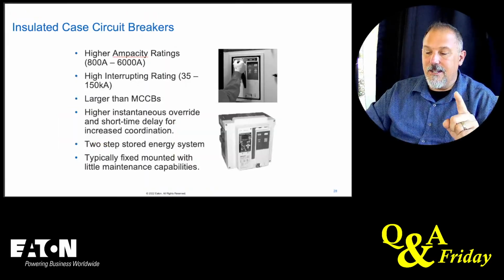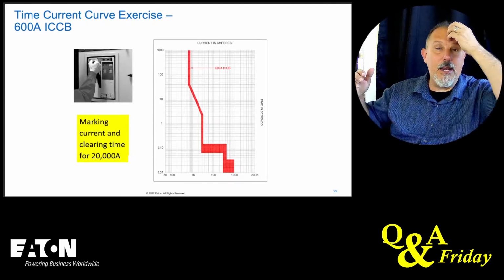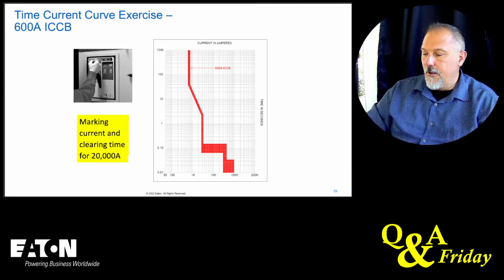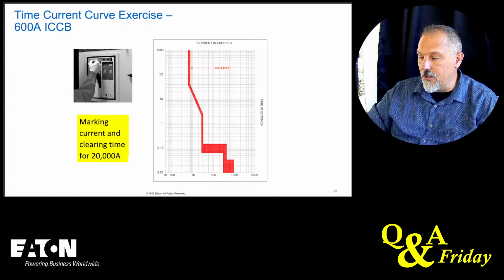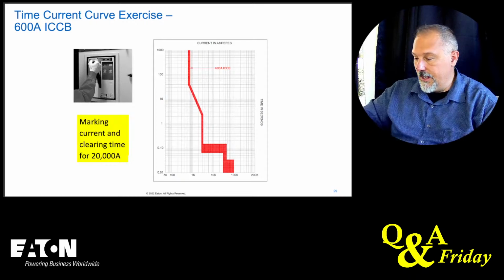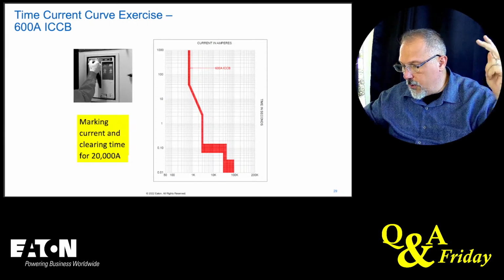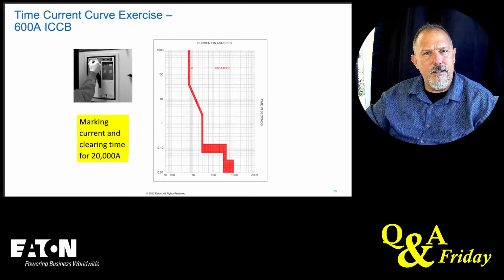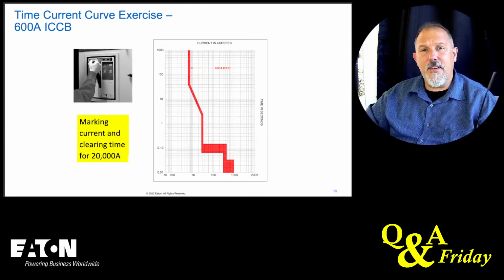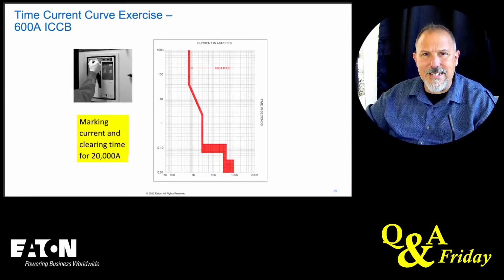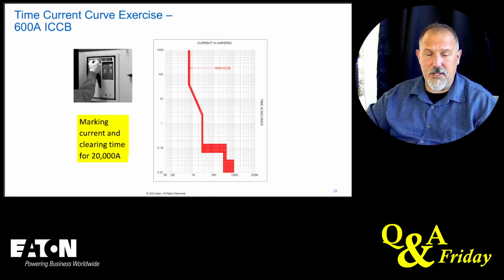Now, an insulated case circuit breaker, 600 amps. So this would be like an 800 amp frame adjusted down to 600. There's your point. That's actually 0.1. There's 0.2. So you're actually around 0.16 seconds. Definitely not current limiting here, but look at the instantaneous region. Your instantaneous region is 0.01, 0.02, 0.03 seconds. That's the instantaneous on this time current characteristic curve for an insulated case circuit breaker. If I'm telling you it's going to take 0.03 seconds to open in the instantaneous region of this breaker, is it current limiting? You should be able to answer that question based on what I've told you.